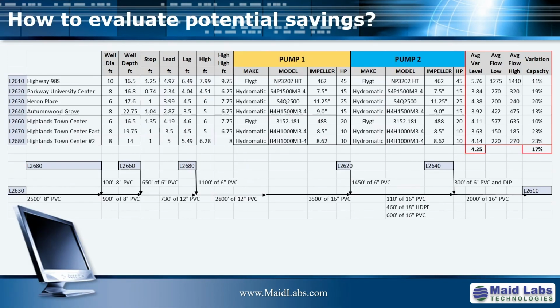We have a test bed in Florida with 7 lift stations where they are analyzing data right now to see how much money they will be saving using a flow-based operating system. In their case, when the flow rate is low, they can increase, on average, the level of operation of their pumps by 4.25 feet. The average increase in pump capacity because of the change of head is 17%.